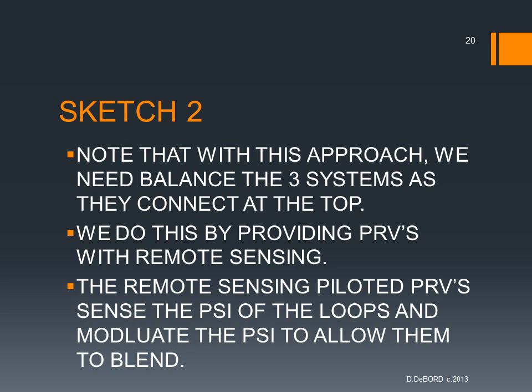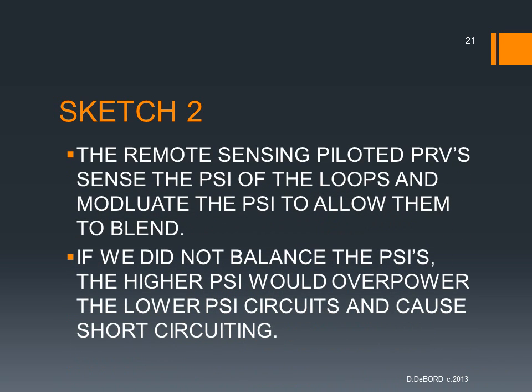We do this by providing PRVs with remote sensing piloted valves. These remote sensing piloted valves sense the pressure of the loops and modulate the pressure to allow them to blend. If we did not balance the PSIs, the higher pressure would overpower the lower pressure circuits and cause short circuiting. You can't push the low pressure side into the high pressure side. The high pressure will overrun it and you will not be able to get that water to circulate properly.